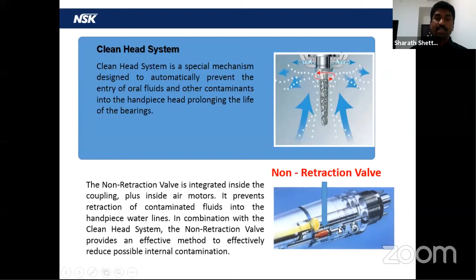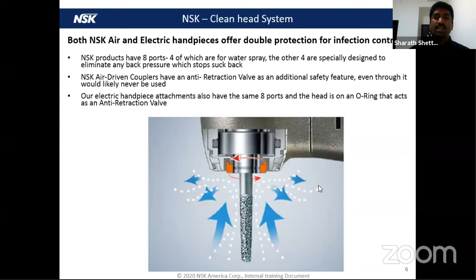Okay, so this is something you need to know about the clean head system and non-retraction valve. As I informed, all NSK handpieces come with the clean head system inbuilt. You don't need to worry. Only for the non-retraction valve, you need to go for the coupling type. Now, I'm sure you must be wondering, just for this non-retraction valve, should I buy the expensive handpiece, which is like 30 or 35,000 in the Indian market, or should I go for an Optic handpiece? No, it's not like that.